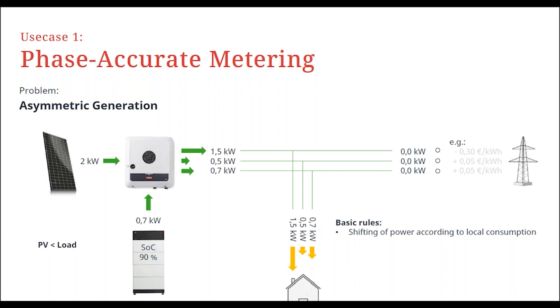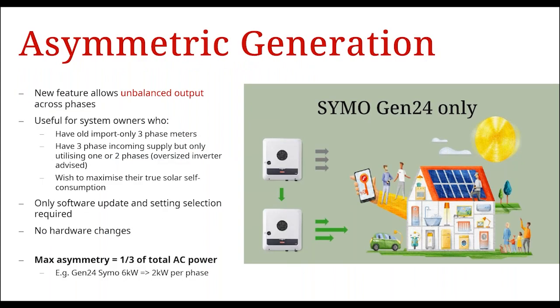And with those older meters, you will be charged for the energy that's being imported, in this instance, on phase one. With phase accurate metering and with the asymmetric generation from the inverter, we're able to supply each of the phases as the demand increases and decreases. This means that you have net zero at the grid. You physically have reduced the issue of unbalance, and as a result, you should improve the billing situation you see with those older meters. The solution is also beneficial to an increasing number of new build sites where you have a three-phase connection to the property, but only have your domestic loads on one of the three phases.